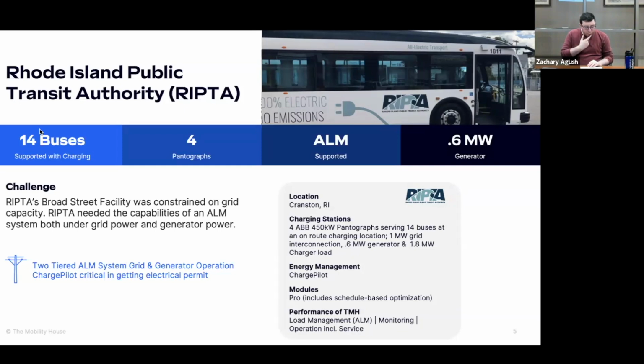As we were putting the design for the site together, we also thought through the megawatt interconnection and the mobility house solution to regulate charge flow at the site, but there was still the concern of overall site redundancy and continuity of service. So despite everything we put in, we still decided to put in a 600 kilowatt diesel generator.